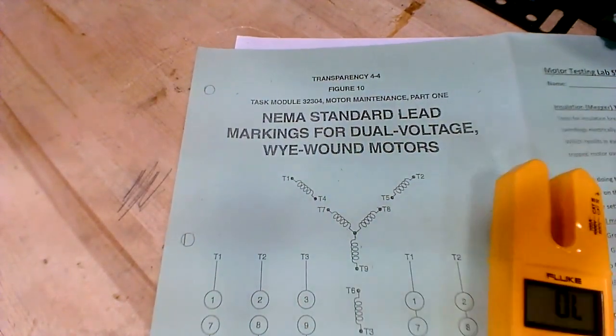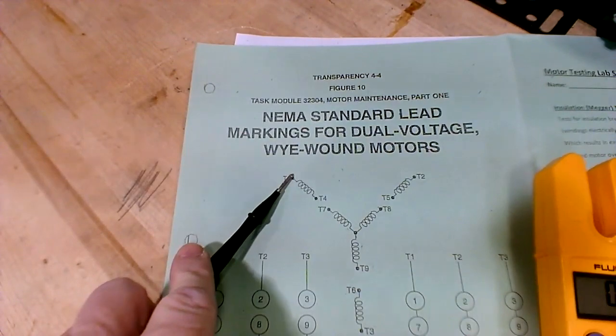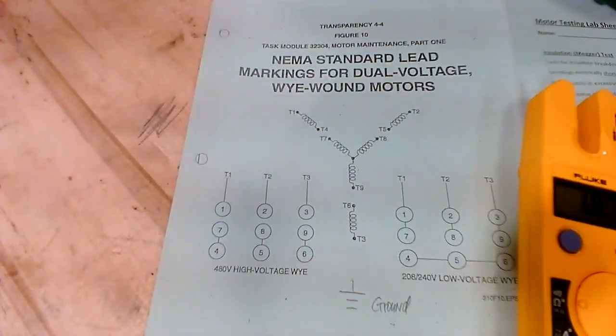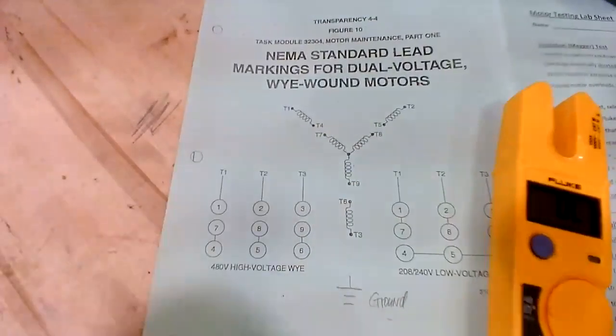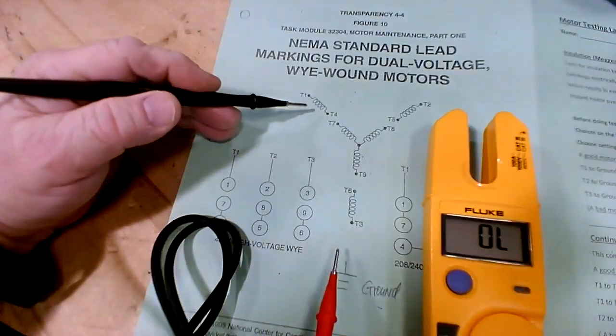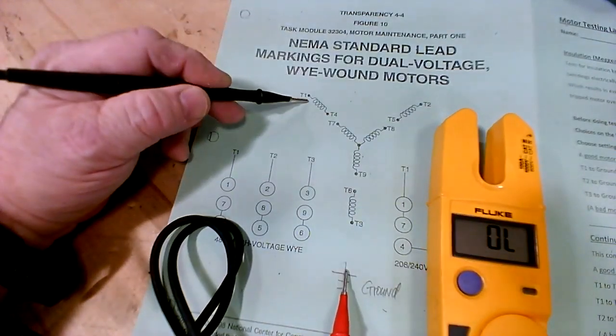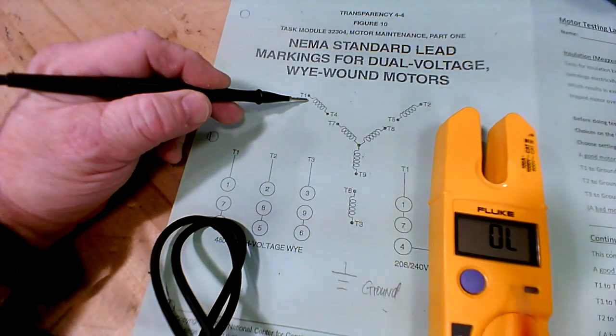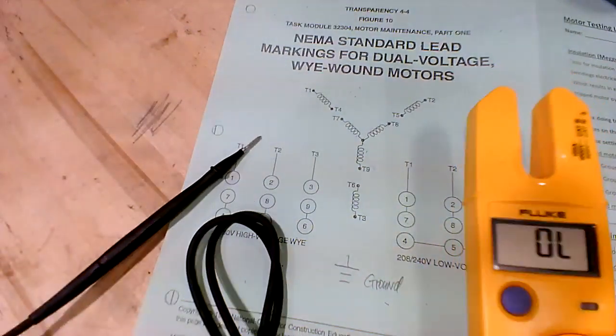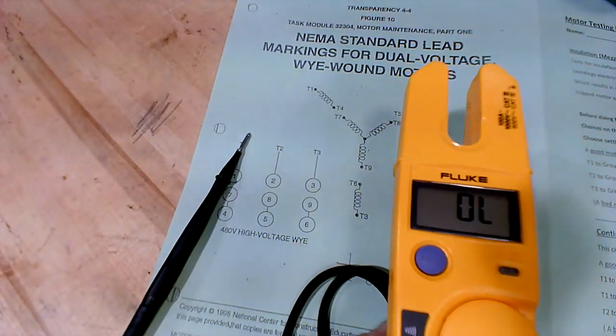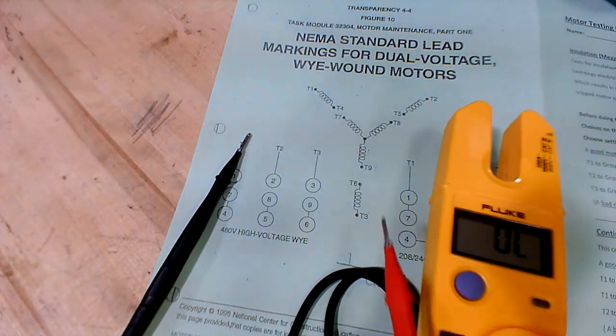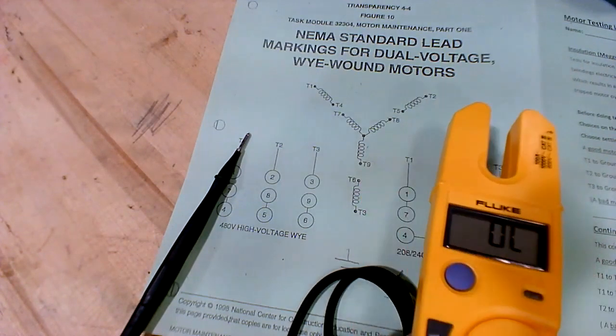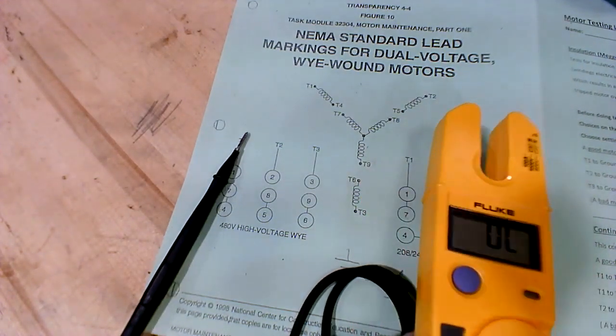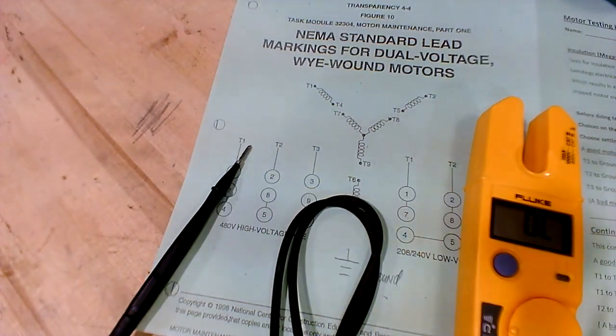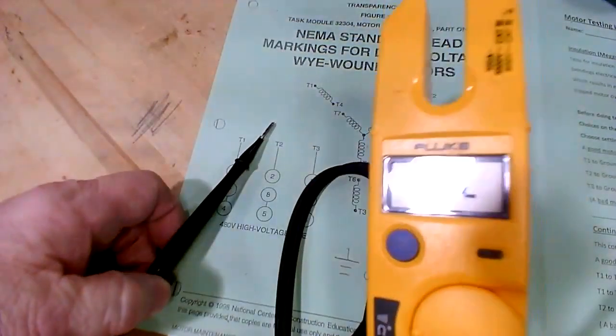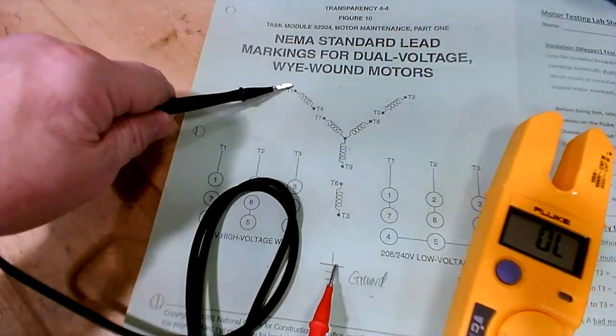have a short circuit to ground. And if you read from T1 to ground, in some cases, when you read from a leg to ground, sometimes it will be a high resistance just above the capability of the meter to pick it up. What do I mean by that? This meter won't read higher than 1,000 ohms. It says 1K, see that? You can have a high resistance ground in here that can cause problems. It can be higher than 1,000. It can be up around 2,000 or 3,000. It can be 500,000 ohms and still be a problem. Seriously.